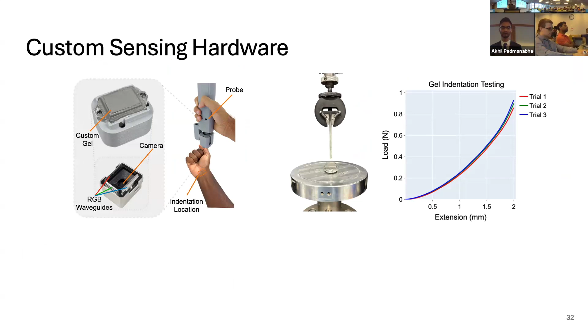So to start off with, we designed some custom sensing hardware. Our custom sensing hardware consists of highly elastic gels to minimize deformation of the skin during contact. We characterized our gels using an Instron indentation testing machine with a spherical indenter and Hertzian contact theory. Our custom gels have a Young's modulus of about 130 kPa. For reference, the Young's modulus of skin ranges from tens of kPa to 3 megapascal. This means that we're likely not deforming skin that is more rigid, but we are likely deforming softer areas of skin. To ensure that the deformation is constant when taking multiple readings, we outfit the probe with a load cell to keep the normal force consistent.